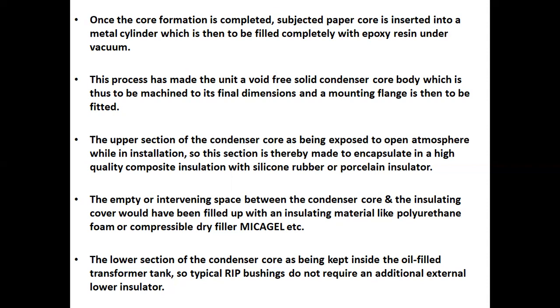The upper section of the condenser core, being exposed to the open atmosphere in installation, is encapsulated in a high quality composite insulation with silicone rubber or a porcelain insulator. The empty space between the condenser core and the insulating cover is filled with an insulating material like polyurethane foam or compressive dry filler, mica gel, etc.